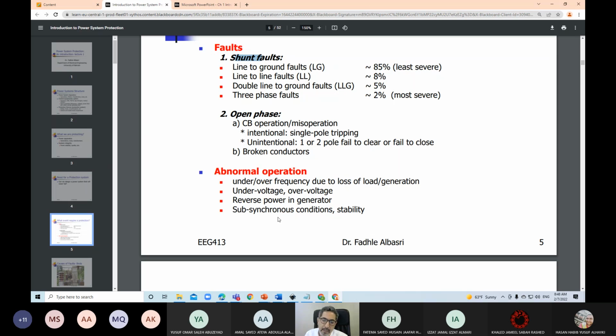You could have over or under voltage situations. It's not due to a fault. Or it could have a reverse power, like you lost the turbine suddenly, but the generator is still connected to the system. The turbine that drives it gets faulty, the steam valve closed, or the flame has been damaged, or the gas intake to the gas turbine is lost. So you lose the turbine, but the generator is still connected to the system.